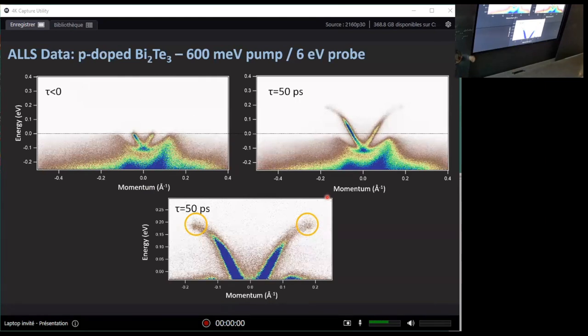Now, before moving to the next slide — with this current analyzer, without moving the sample, we can acquire electrons emitted within a cone of emission of 60 degrees. Usually in ARPES we detect electrons only along the slit direction, so let's say plus or minus 30 degrees, which we call Kx, the parallel momentum along the x direction as a function of binding energy. However, you can also deflect the photoemitted electrons, so you can detect them at different Ky, and reconstruct what is called the Fermi surface.